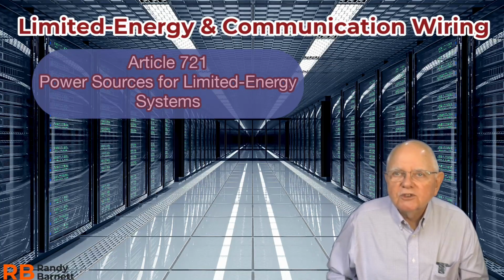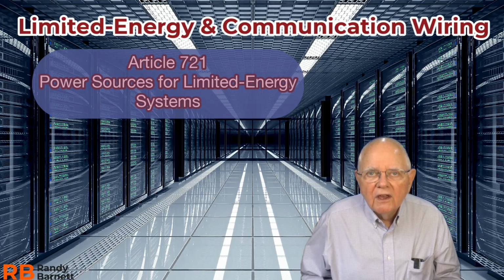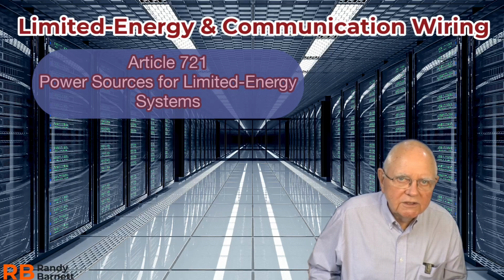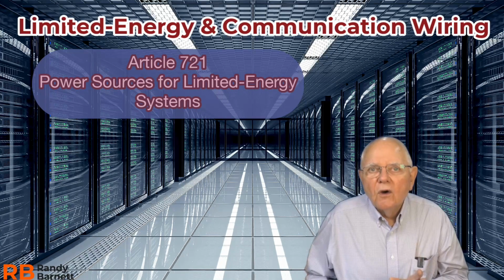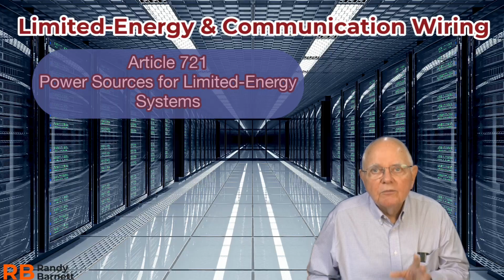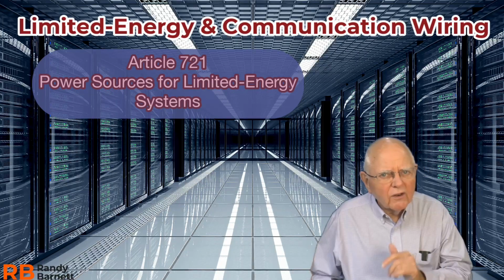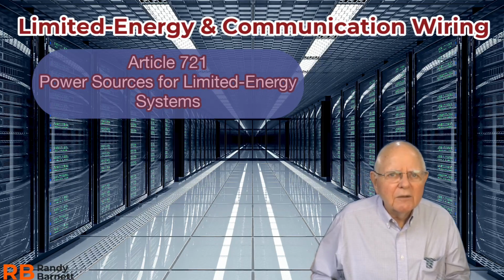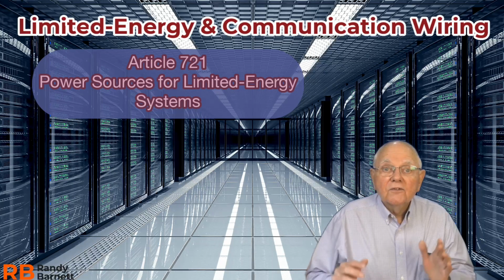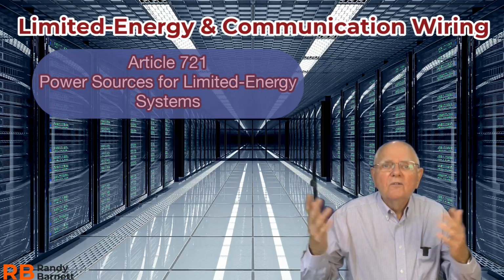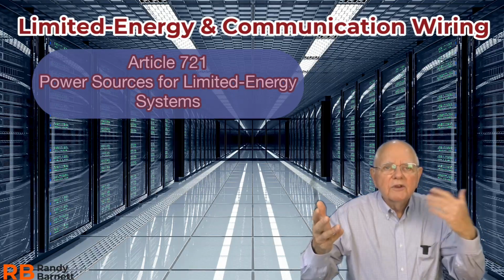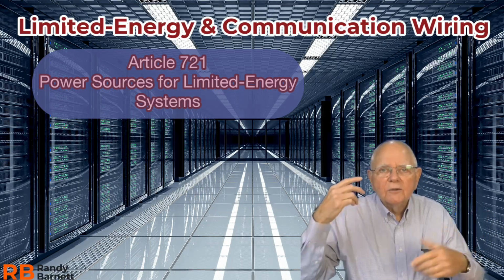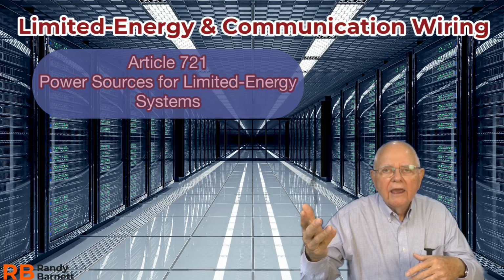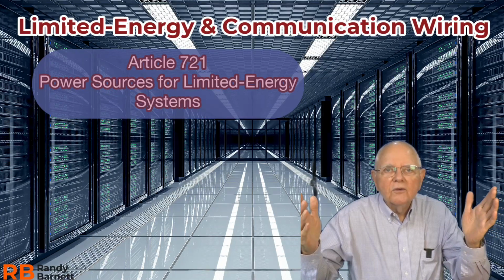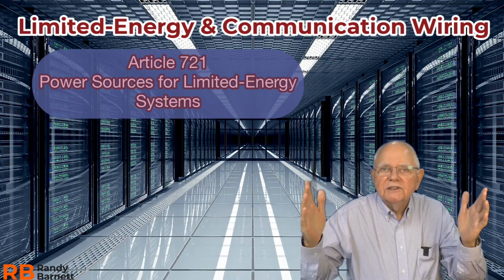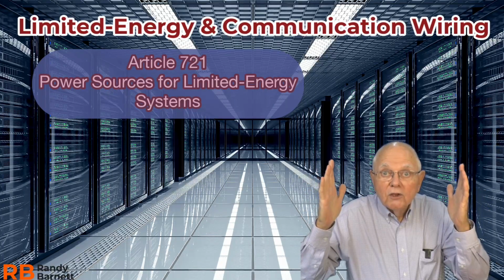Class 2 and 3 power sources have to be listed, it tells us. Then it mentions Class 4 power sources. Class 4, up to 450 volts, peak AC or DC. 450 volts, and it's still considered limited energy. And what we have with these Class 4 fault mitigated systems, we have a transmitter and receiver. So we're talking about the power source, the transmitter, and the cables, of course, that run in between. 450 volts AC or DC applied to those cables. And you say that's limited energy.